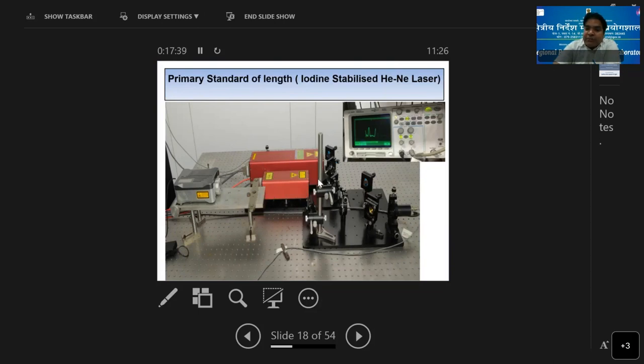And from here the beam comes, and we make a kind of interferometer with a beam splitter, and we calibrate another laser with this one. So I will tell you again, this is a 633 nanometer iodine stabilized helium neon laser. We call this iodine stabilized because the laser is stabilized on frequency components in iodine. So we fix the frequency on one of the components A, B, C, D, E, F, G, H, I, but the most prominent are D, E, F. So we fix on D, E, or F and lock the frequency and calibrate another laser, and that laser will be used at lower places. I will tell you later in another presentation how that works.